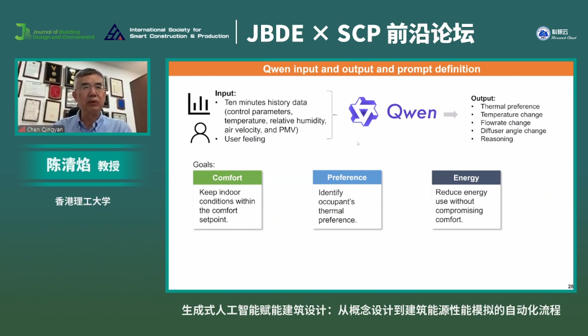What we do is validate this in our lab. This is a very simple lab, one room. We put 2 desks there, and also 2 dummies. We measure the temperature distribution in several locations, and this is the boundary condition. We evaluate the thermal comfort at 3 different levels: ankle level, chest level, and head level, for a seated person. Then we want to see how the control parameters generated by the model—air supply temperature, flow volume, and angle—perform.